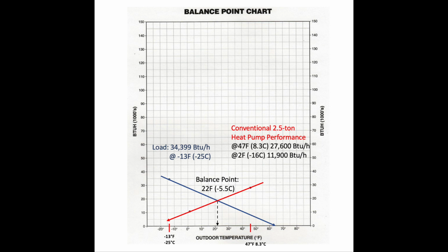I live near Ottawa. My outside design temperature is -25°C. It does get colder than that here, but my load at design is 34,399 BTUs. So I plotted that on the chart at -25°C or -13 Fahrenheit. And I drew a line down to 65 or 18 Celsius. That's the theoretical point where no heating or cooling is required. So we call that the load line.